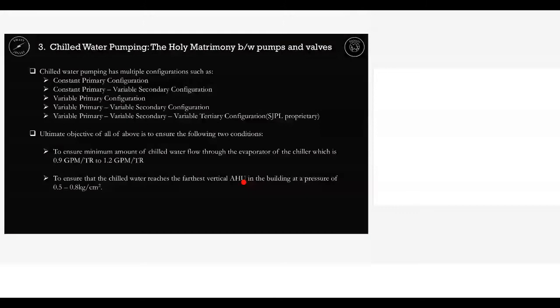So when many valves are closing by the IoT command, after understanding that they are not required, the pressure in the system increases. And the sensors integrated to the IoT as well as the building management system will detect the increase in pressure in the line. So now let me reduce the VFD, the variable frequency drive frequency, of the chilled water pump. It should be a VFD pump, a variable speed pump, to exploit this benefit. Then only will you get the savings. So keep this number in mind. It is a very important number for a building.